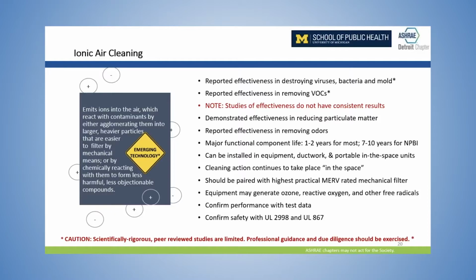The ionizing air cleaners perform somewhat similarly. These are actually a derivative of older electrostatic air cleaners that you may be more familiar with. Instead of charging small particles and having them agglomerate and then precipitate out on collection plates, these actually send those ions out into the airstream where, similar to the photocatalytic oxidizers, they interact with contaminants in the space.